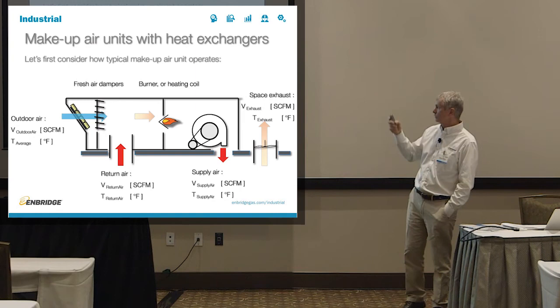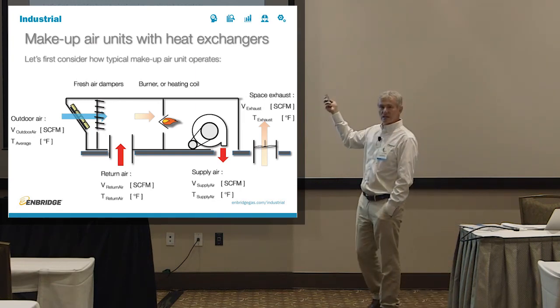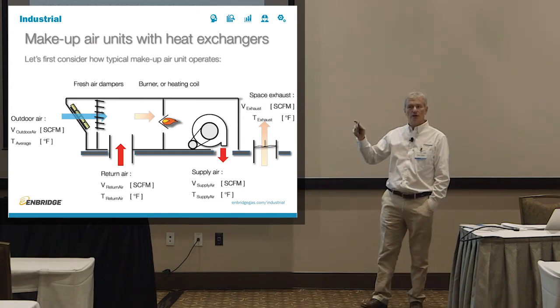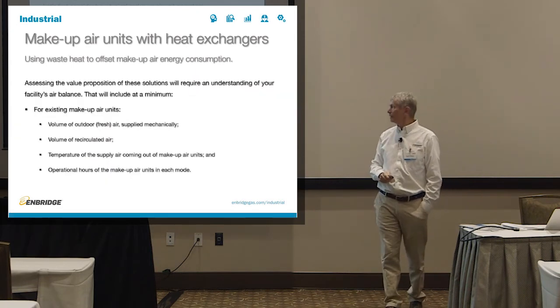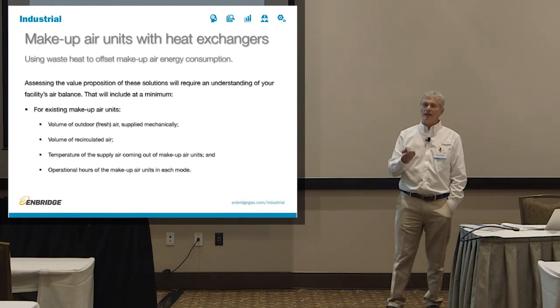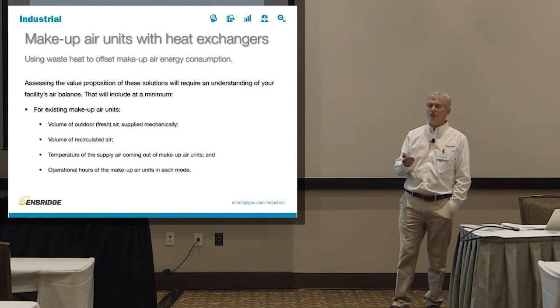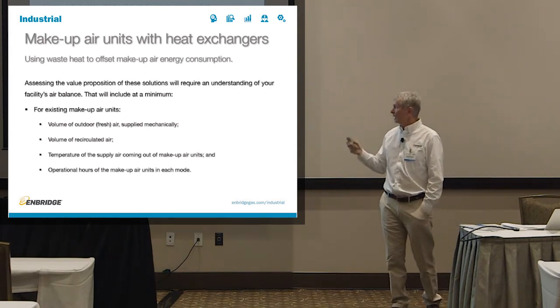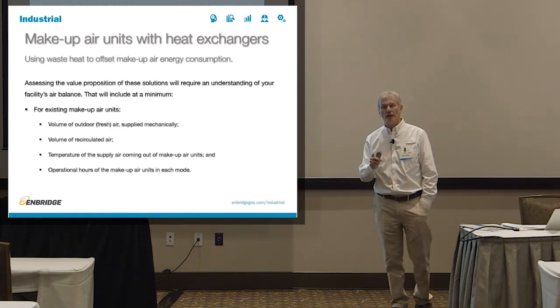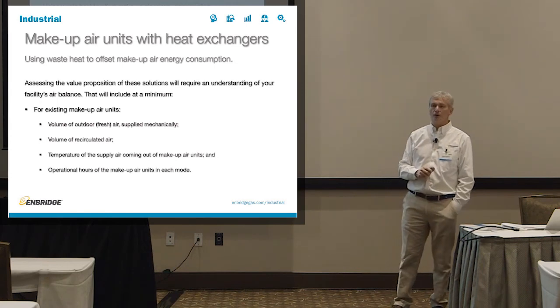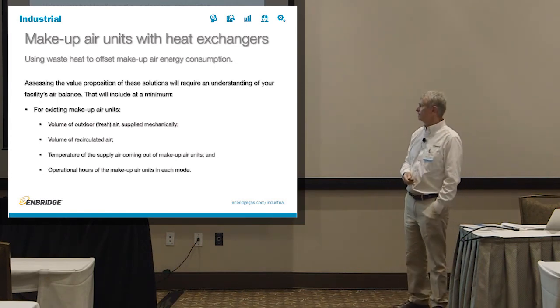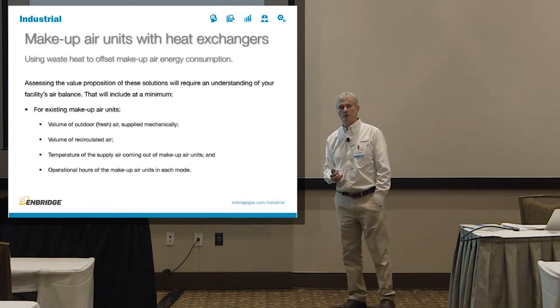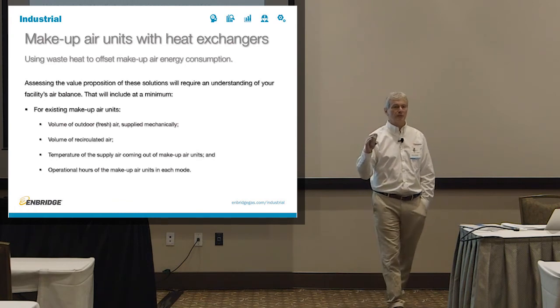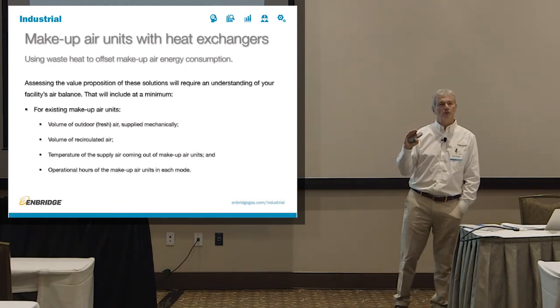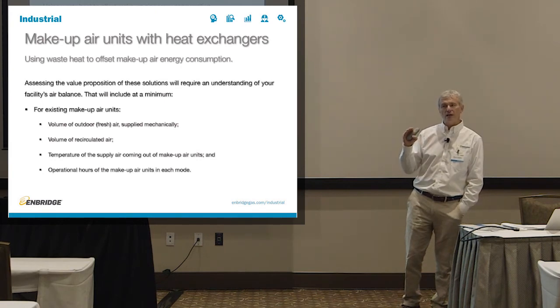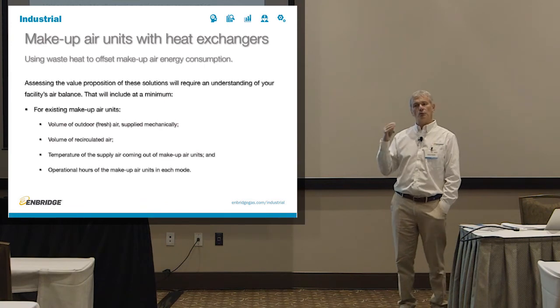So what we really need to know out of all of this is the space exhaust as well. I forgot to mention that, how much space exhaust you have. Those two things have to be balanced. So what you really want to know before you go into the makeup air unit upgrade is how the makeup air unit works and what the energy is used for. How much makeup air you have, how much fresh air you actually have, and how much recirculated air you have. Where are those dampers set? What's the temperature of the supply air coming out of the makeup air units? So your space might be 70 degrees F, but your makeup air could actually be set for 90 degrees F to come out of the unit. So the energy going into those CFMs of fresh air coming into the system is for up to 90 degrees F, not 70.